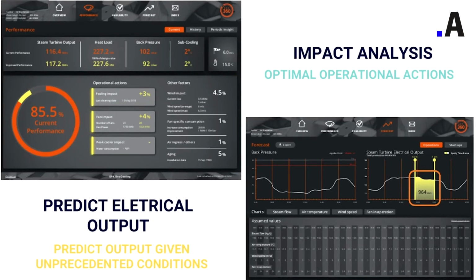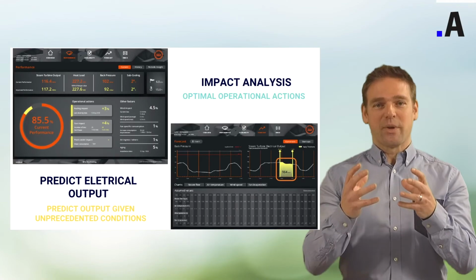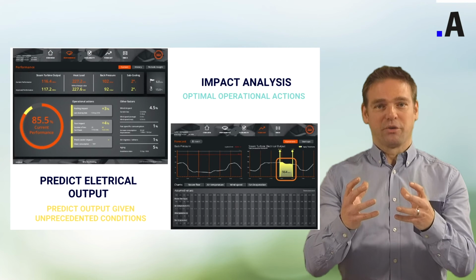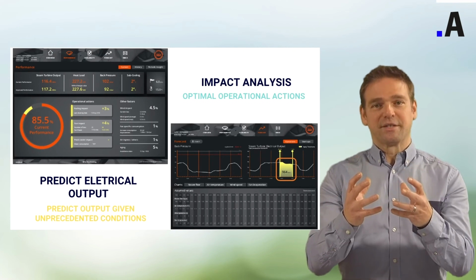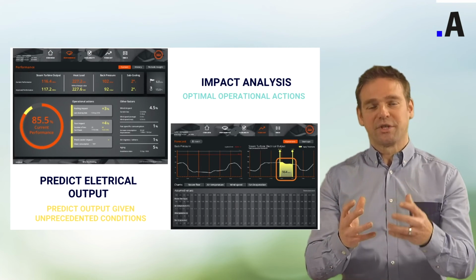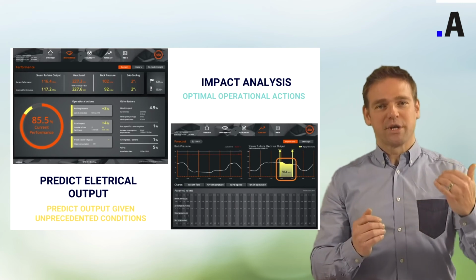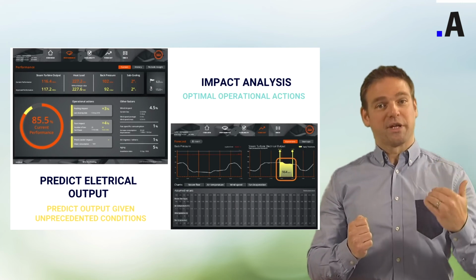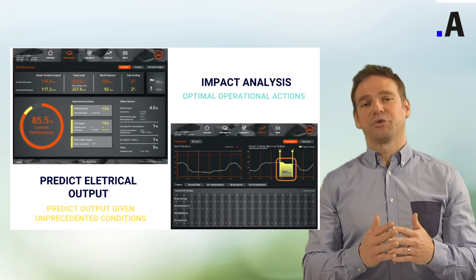We started by building a theoretical model that grasps the relationship between steam flow and back pressure, creating a simple model that gives us theoretical insight into how back pressure relates to steam flow and temperature, for a number of constellations in numbers of fans used.